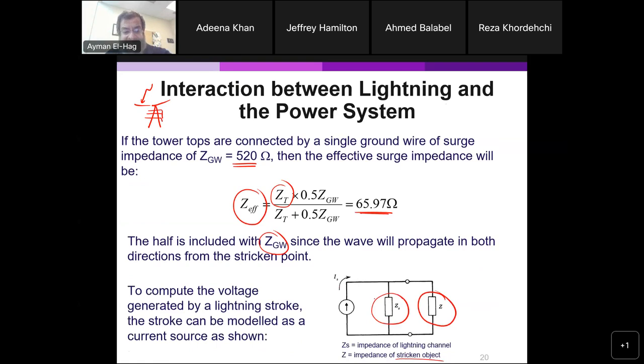Now ZS is the impedance of the lightning channel itself. So you have the lightning channel in parallel with the impedance calculated here, which is the surge impedance in parallel with half of the ground wire impedance.